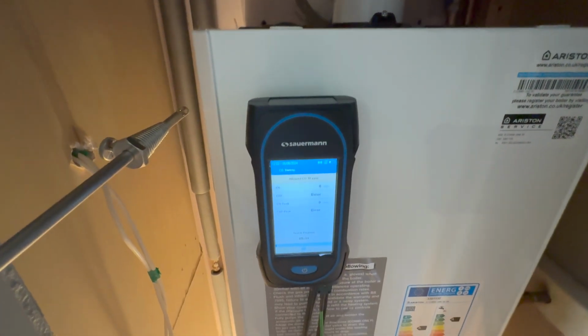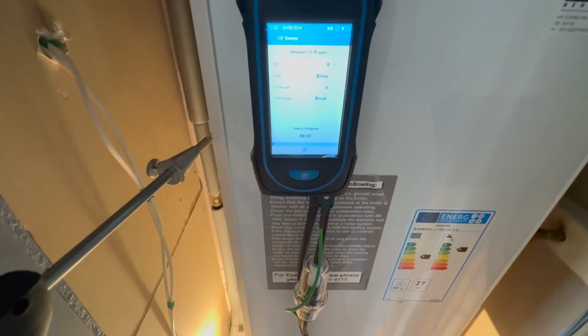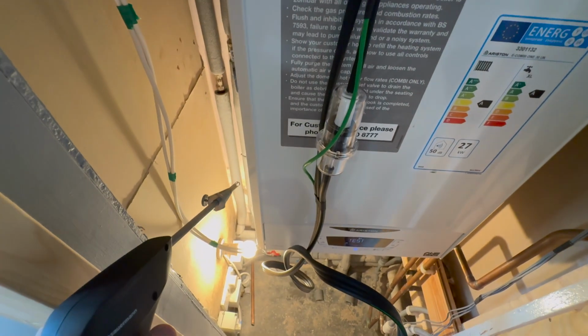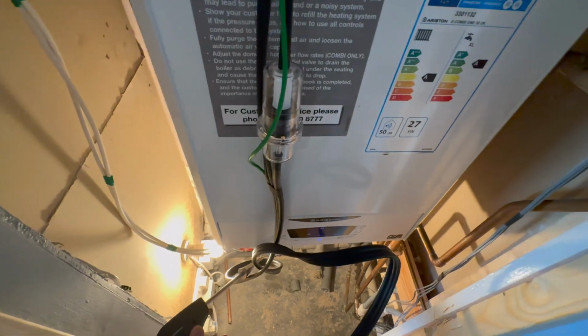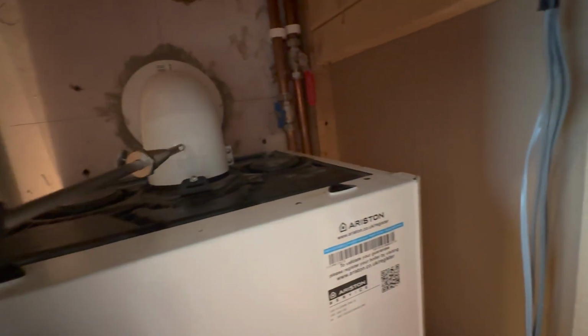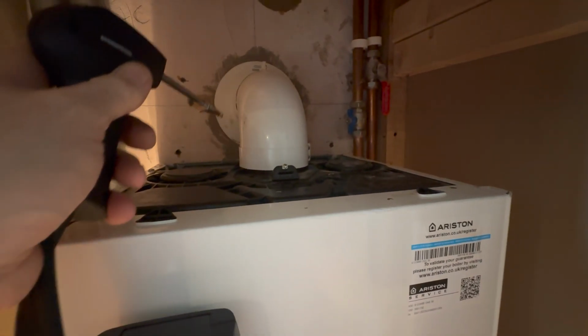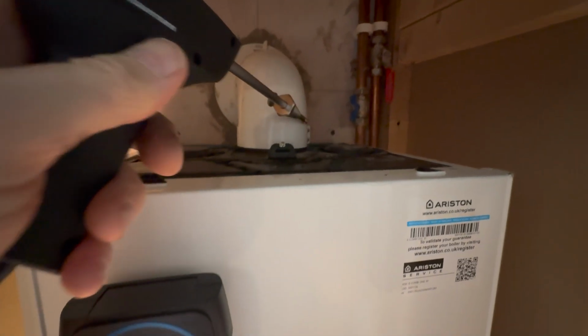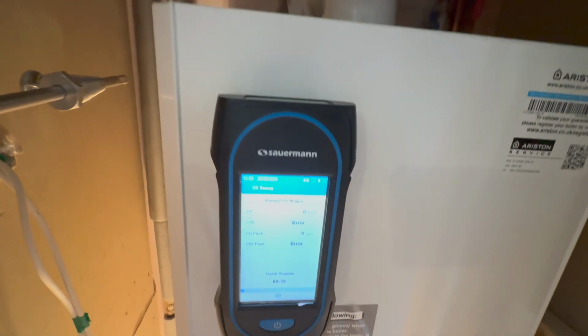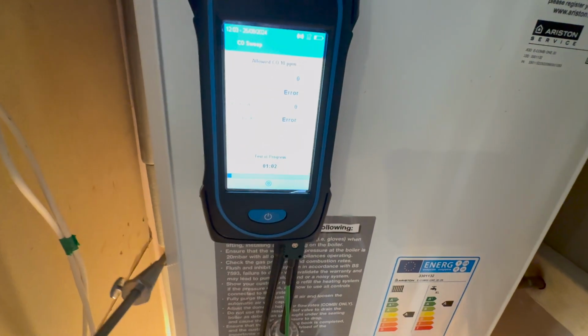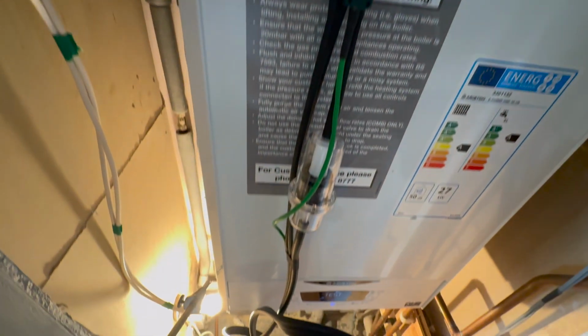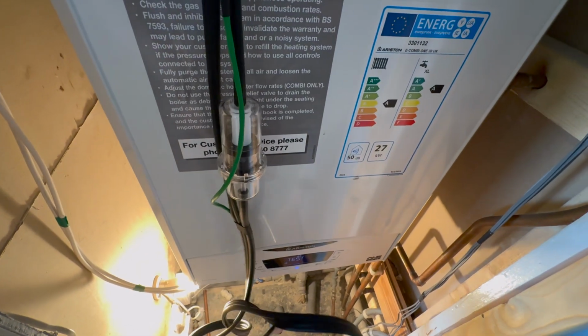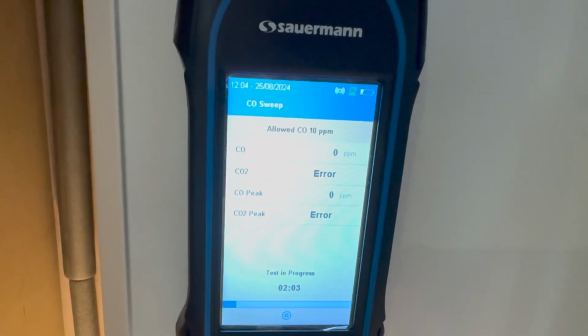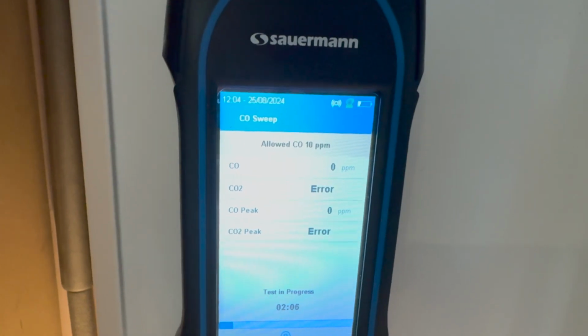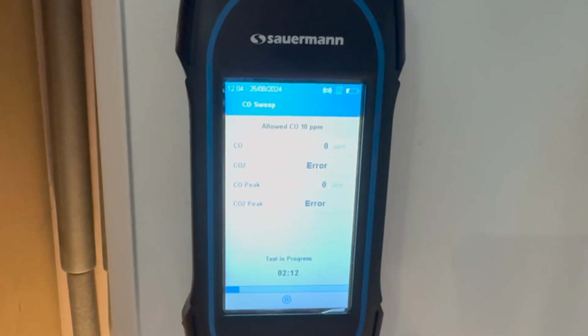Now the last analyzer setting is sweep test. So we've got to go around the casing of the boiler, around the turret, for 2 minutes and see if we get any readings on our CO, which we should have less than 10 parts per million of CO. So our 2 minutes are up on the sweep test and we've got zero CO. So I guess that's a pass also.